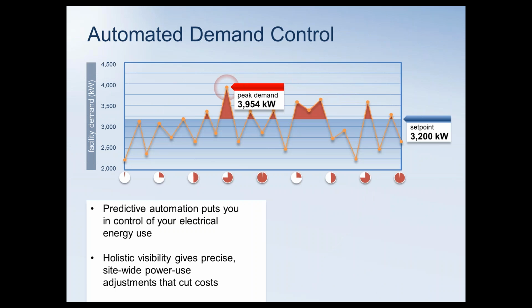This next slide is showing basically a facility and what it would look like. You can see the 3,954 kW peak demand. That could be that one 15-minute time period during your on-peak when you had a coincidental peak, and you would pay, in our case at Canon, $11 a kW. We would have paid $11 times 3,954 kW. The peak demand, the coincidental peak demand charge, is basically the rate at which you're consuming power, not the power you've actually consumed. So you could visualize that driving down the road at 100 miles an hour versus driving down the road at 55. You're going to get much better fuel economy. At 55, you're going to get to the same place. It's just going to average out over time. So that's what we were looking to achieve with the demand control.